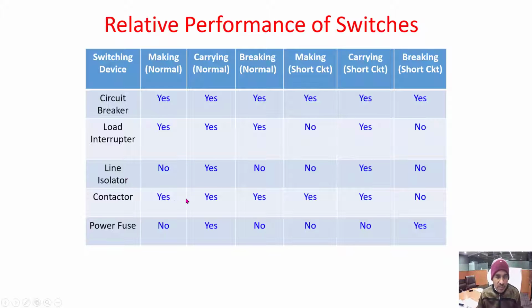Then the line isolator. The line isolator cannot make even under normal conditions, and it can carry the currents under normal conditions. Again, it cannot break under normal conditions. Similarly, it cannot make under short circuit conditions, nor break. Only it can carry the currents. That is what the line isolator will do.